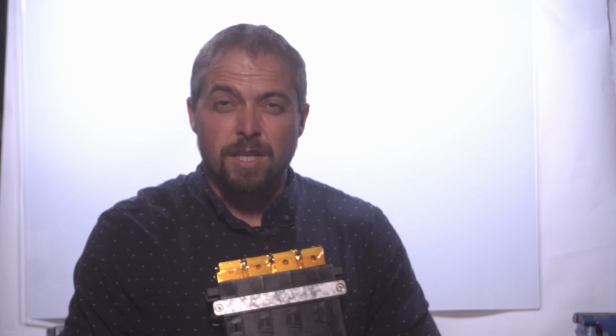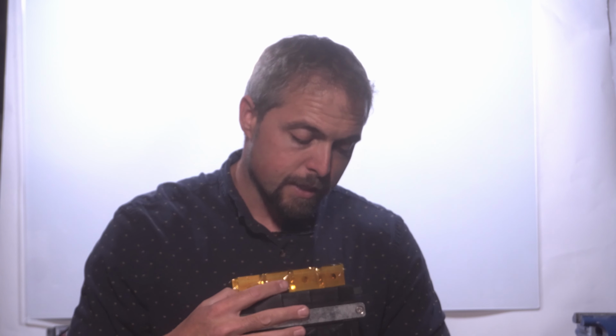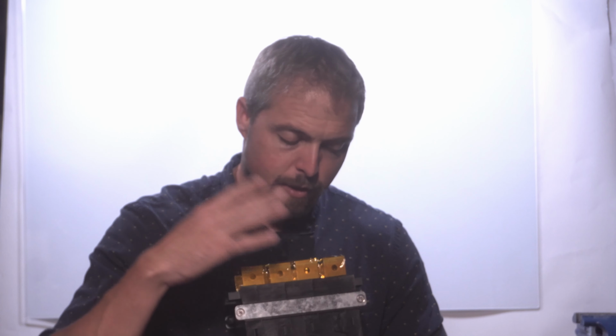In general, the data sheet for this specific cell has always said that if the internal resistance doubles, that cell is ready to be recycled and you should replace it. It's not a hard fast rule - a lot of suppliers in China are starting to push away from that and allow a higher internal resistance. As long as your BMS can account for that during high discharges, that's fine, but you may get some low voltage warnings more frequently just because of the internal resistance of the cells.